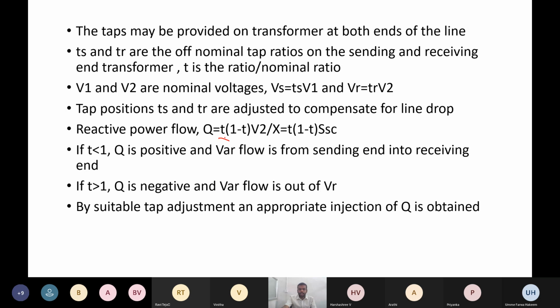So Q is given by T into 1 minus T into V square by X. So we can control the flow of reactive power into the circuit, or we can absorb the reactive power from receiving end to sending end by using suitable tap changes. So suitable tap adjustments will be done by using our T. How? By using Ts and Tr. So Ts and Tr are off nominal tap changing ratios. That will depend upon T, and by using suitable tap positions, we can control reactive power injection into our circuit.